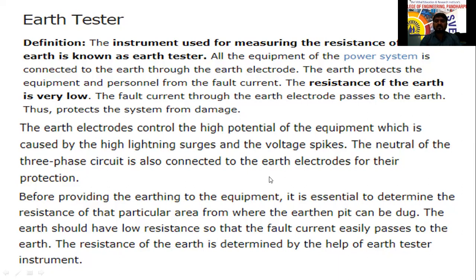Without checking the resistance of that earth, how will you know it? If that area earth resistance is high, it may be 10 ohm, 15 ohm, meaning it has some opposition. So the resistance of that one should be less than 1 ohm only. So the earth should have low resistance so that fault current easily passes through, and the resistance of the earth is determined with the help of the earth tester.